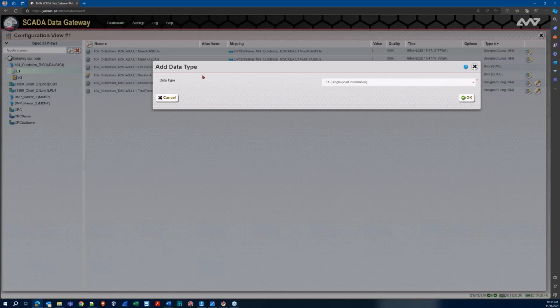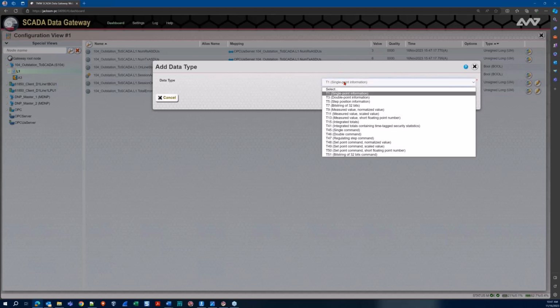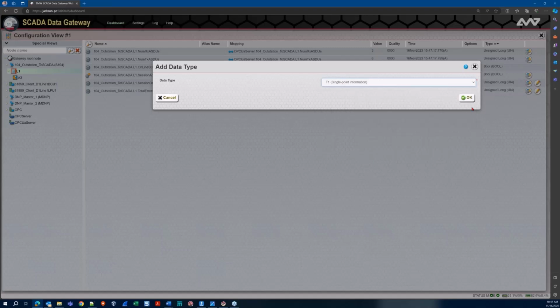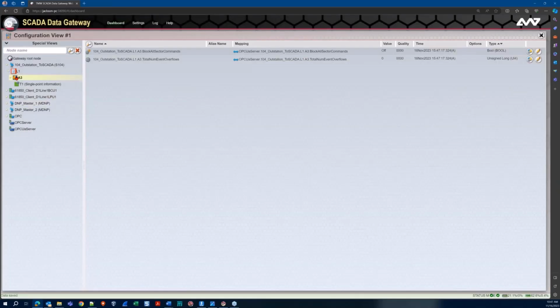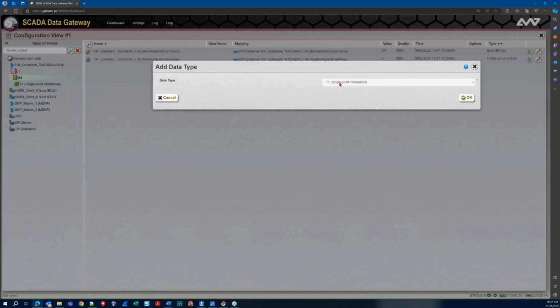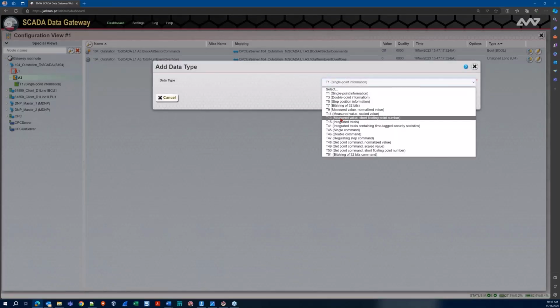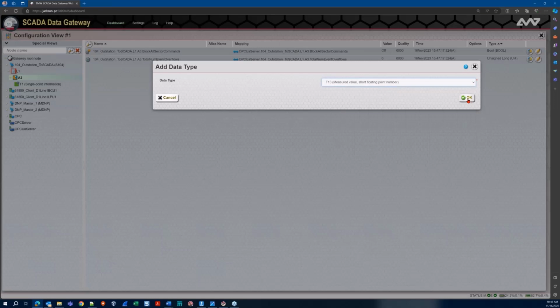Now I have the opportunity to add what type of data I'm going to be sending out of my 104 outstation. Here's the list of available options. The T indicates the type, and you'd need to get familiar with the 104 documentation to know the numbers — T1 corresponds to single point, whereas T13 would be floating point. We'll be working with both of those, as well as, once we get into the controls portion, T45 single command. So I'll start out by adding single points, and additionally I also want to make sure I add in those T13 measured values as well.